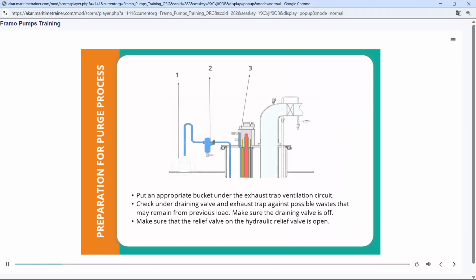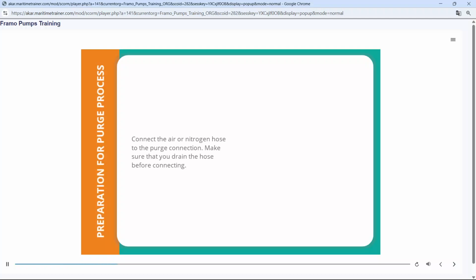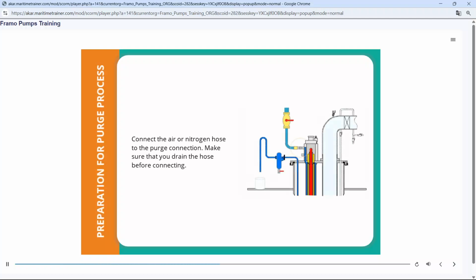Preparation for the purge process. Put an appropriate bucket under the exhaust trap ventilation circuit. Check under the draining valve and exhaust trap for possible waste that may remain from the previous load. Make sure the draining valve is off. Make sure that the relief valve on the hydraulic relief valve is open. Connect the air or nitrogen hose to the purge connection. Make sure that you drain the hose before connecting.